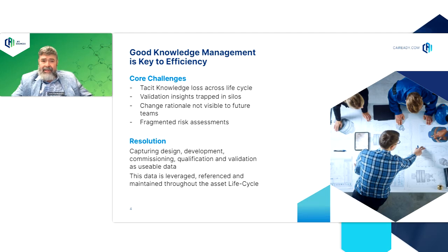Over time, this leads to fragmented risk assessments, duplicated testing, and limited visibility into historical decisions. Digital validation technologies address these issues by ensuring information generated through the life cycle is captured as structured, reusable data. Design, commissioning, qualification, and validation outputs are connected and maintained across the life cycle. Instead of knowledge being locked in documents, it becomes accessible, searchable, and reusable, which significantly improves operational efficiency and risk management.